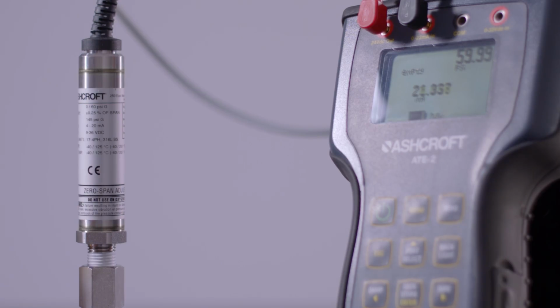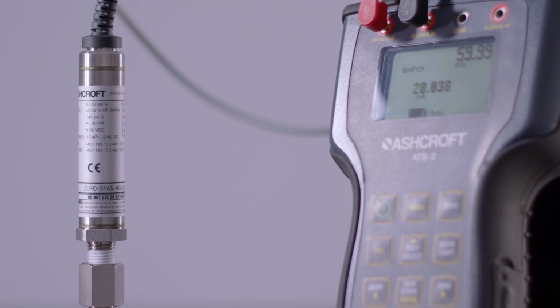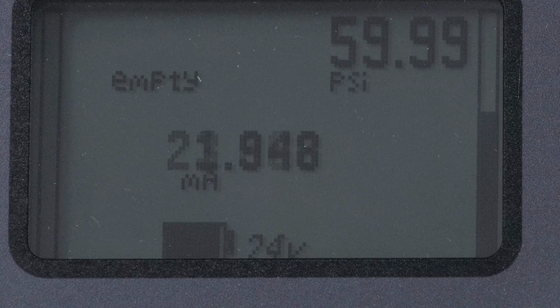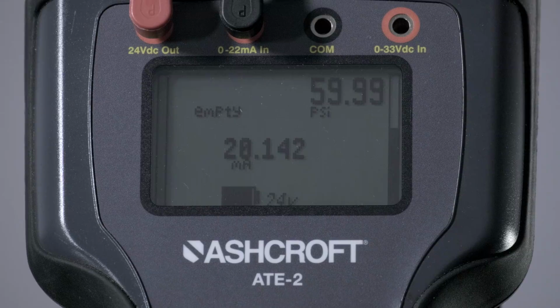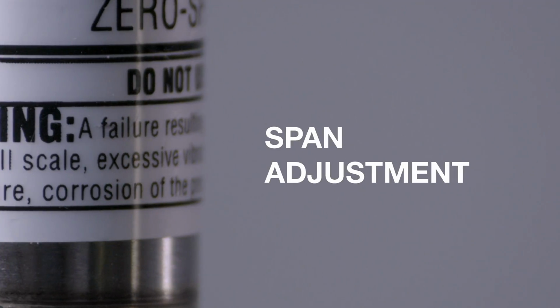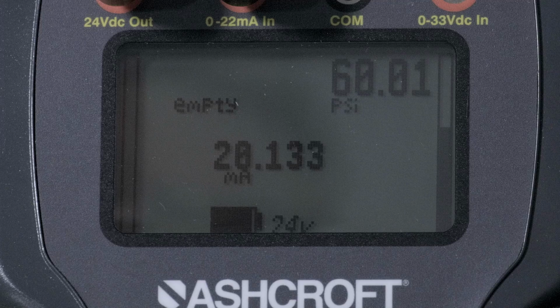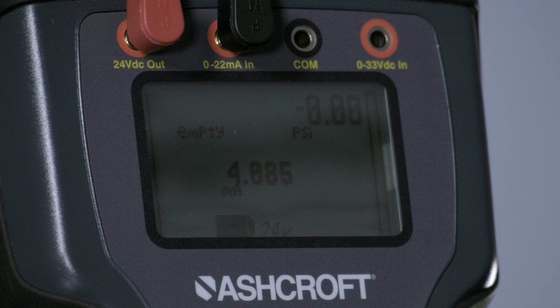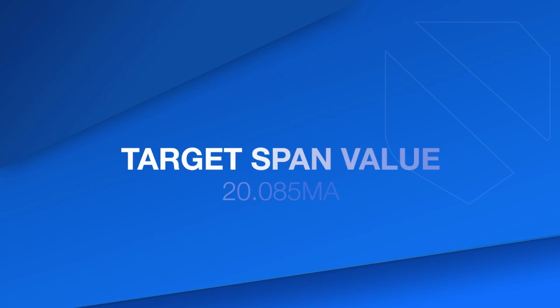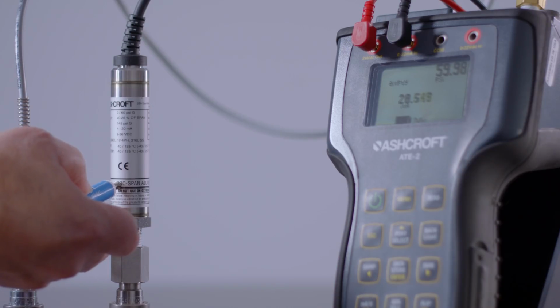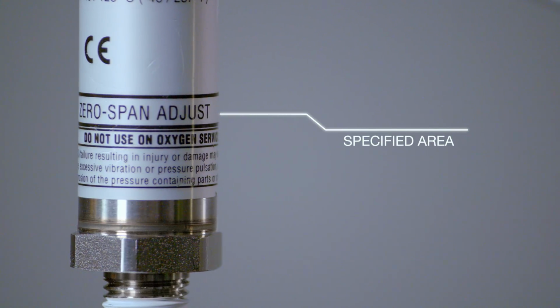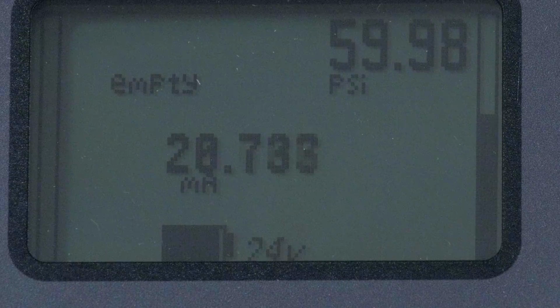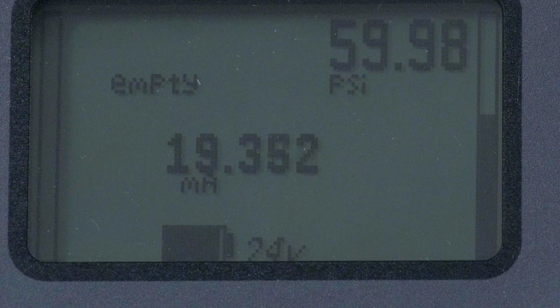When the calibration mode has been activated, the output signal on the transducer will drive from over range to under range. For example, this unit has a 4 to 20 milliamps output, and the signal will drive from 3 to 22 milliamps. Now we will adjust the span value to 20 milliamps plus the offset value we measured at 0 psi, so the target span value is 20.085 milliamps. To adjust, we will tap the magnet near the specified area on the label. In this case, we were a little high, so I will take it up and loop around.